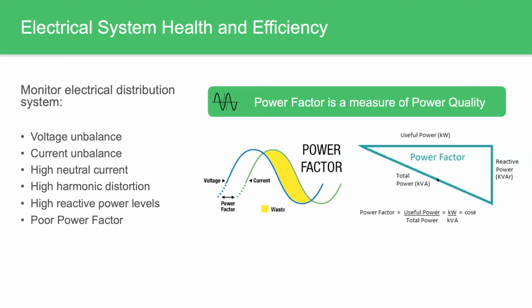Another important measurement is power factor. Many people are very familiar with power factor, but for those that aren't, it's really a fundamental indicator of power efficiency. It's a measure of the flow of current relative to the voltage, as you can see here in the illustration on the slide. When the voltage and current are perfectly aligned, the power factor is at 100% or 1, which is also called unity. During unity, all the available power is active power and there's no reactive power. But when you have loads that are inductive, things like heaters, furnaces, or motors, these cause the current flow to lag behind the voltage.